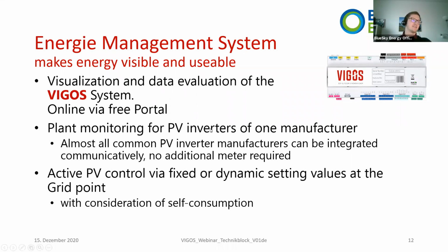Inside this EMS, you can also do active PV control with fixed or dynamic settings. I don't know if you know about the regulations in Germany, because there they have to make sure that, for example, a 10 kilowatt peak PV system will never feed in more than 7 kilowatts. So they have some special regulations there, and for this, we have this function available in the EMS.